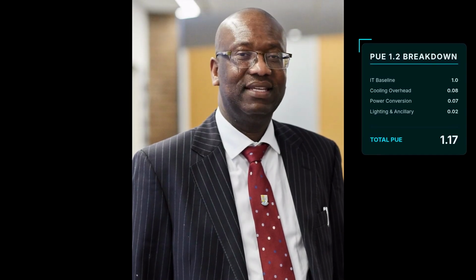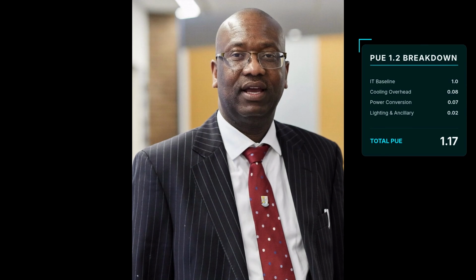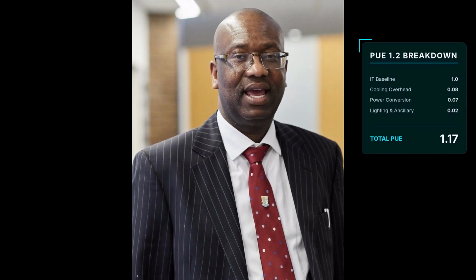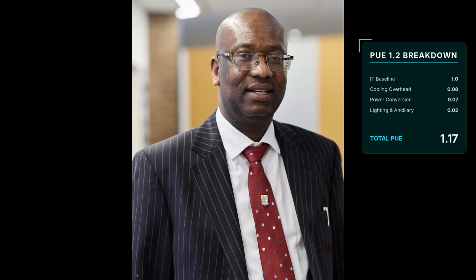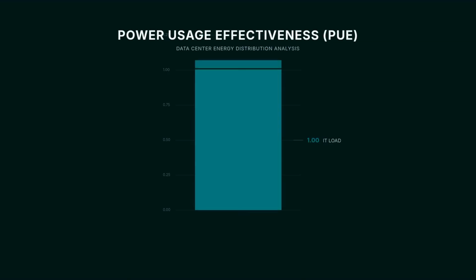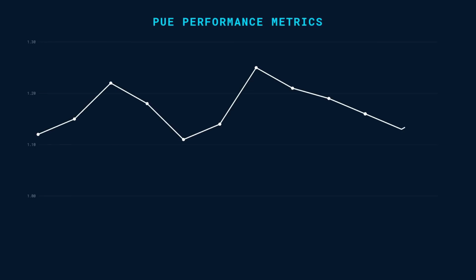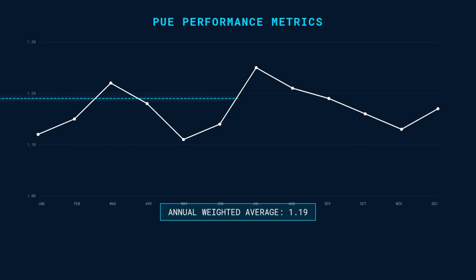Let's break down exactly how we hit that 1.2 target. With an IT baseline of 1.0, our cooling overhead is just 0.08 thanks to the airside economizer. This is the dominant factor in our efficiency. Power conversion from UPS and transformers adds 0.07, while lighting and ancillary building systems account for the final 0.02. This brings our instantaneous auxiliary total to just 0.17. While instantaneous PUE fluctuates between 1.1 in winter and 1.25 in peak summer, our annual weighted average is 1.19, comfortably meeting the 1.2 target specified in the Cloud Core lease agreement.